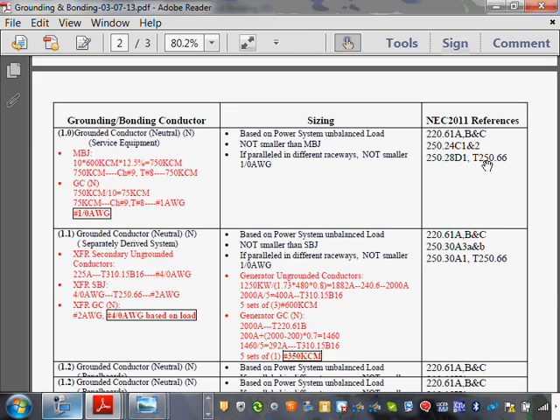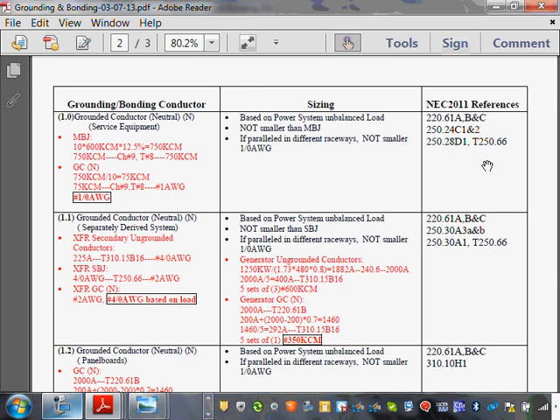So if you guys go to 1.1, it's right on this side for the generator. To size the neutral, you have to size the phase, right? So for generators, you take the 1250 kW divided by 0.8. Anybody know why 0.8? You have to convert kW into kVA. So I converted the kW to kVA, and then I converted it to amps. At this amp level, guys, we're looking at 1882 amps. At this amp level, you don't multiply it by anything, because they call them 100% rated circuit breakers. Has anybody heard of 100% rated circuit breakers? The circuit breakers are 100% rated, and they work. You don't have to derate them. So we take this number here, 240.6, and size your overcurrent protection device, 2000 amp.